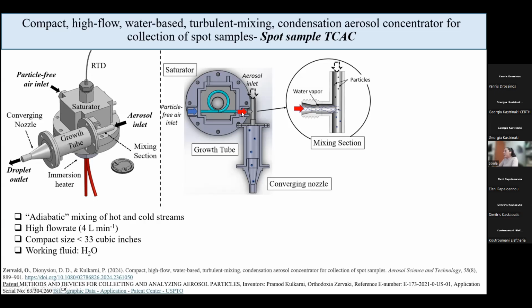This water vapor then enters the mixing section, which is a T-shaped mixing section where at the top we have the entrance of the aerosol flow, which is at ambient temperature. And we have a theoretically instant adiabatic mixing of these two streams that causes generation of supersaturation, where the water vapor goes and condenses on the surface of the particulates. And then we have the droplet formation and the growth that is further enhanced in the growth tube, where more time and space is given for the mixed flow and the droplet growth to happen.